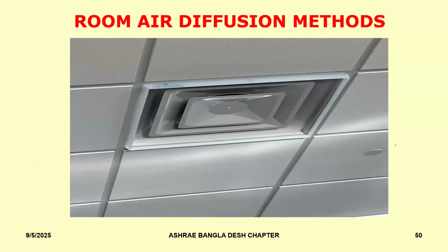When we make four-way diffusers like that on the ceiling, the idea is that we use a principle called the Coanda effect, which actually helps us to spread the air uniformly on all the four sides. Sometimes it leads to what is called smudging. That's because the air is not well filtered. But some architect came out with a clever suggestion that why not we put a coving like that on all the four sides so that the smudging gets eliminated. Well, they did manage to eliminate the smudging, but at the same time they disturbed the entire Coanda effect, and therefore the air started to dump straight down instead of diffusing. So people sitting below that diffuser started to feel uncomfortable drafts. So you need to be very wary about doing things like this.